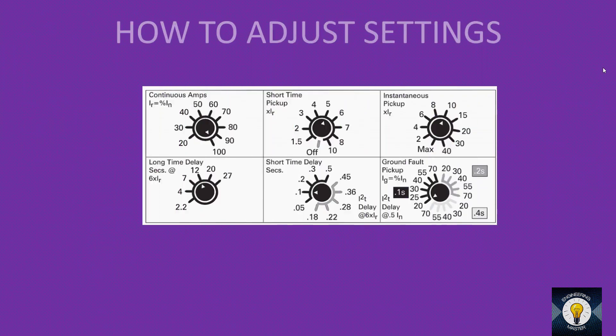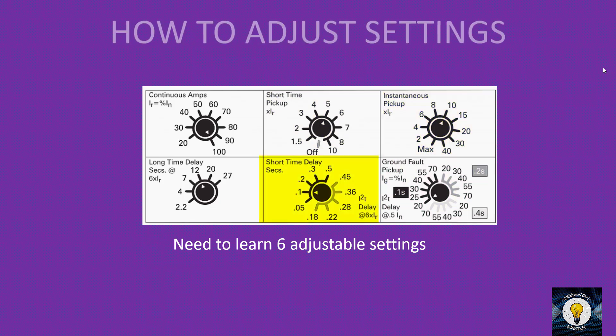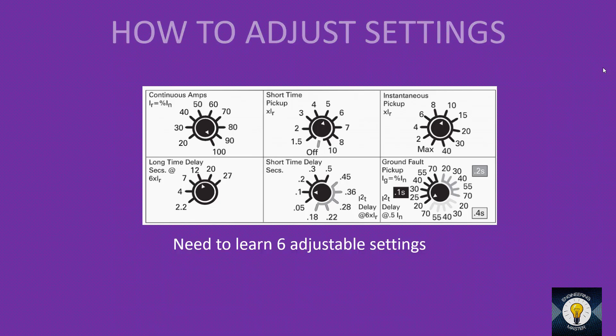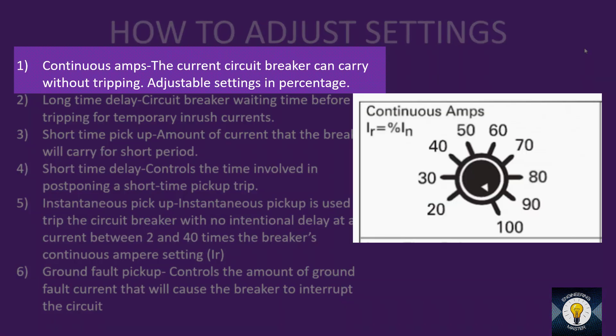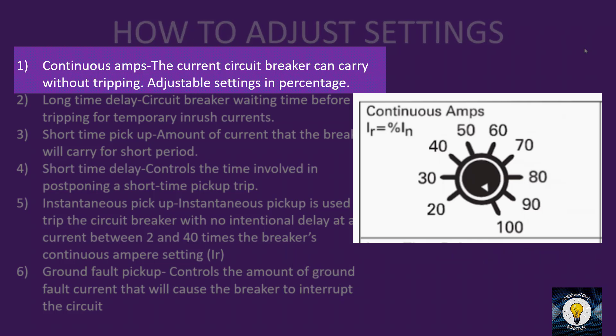The main advantage of MCCB is that we can adjust its settings. There are six types of adjustable settings: continuous amps, short time pickup, instantaneous pickup, ground fault pickup, short time delay, and long time delay. These settings use an adjustable selector switch — you insert a star screwdriver and rotate to different levels. Continuous amps is the current the circuit breaker can carry without tripping, expressed as a percentage from 20% to 100% of the rated current.